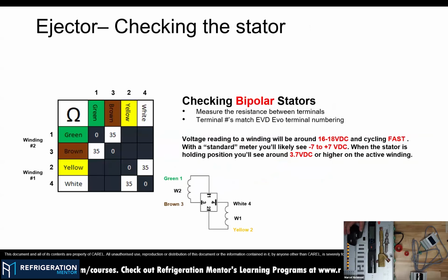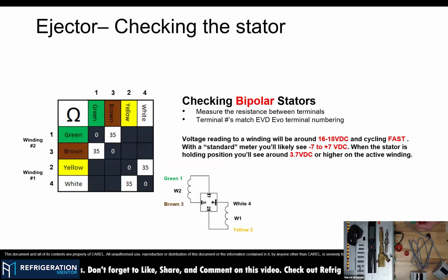Yeah. Okay. And another thing that you can check is the wiring connection. So let's say that you have a damaged wire. Our coils, all of them, have the same resistance: 35 ohms, from 33 to 38 ohms across all the models. So if you need to check if the coil is the problem, because you are seeing a motor error on the display, errors that the valve is not connected, you use the magnet to drive the valve and it's working. So it might be this piece that is damaged.